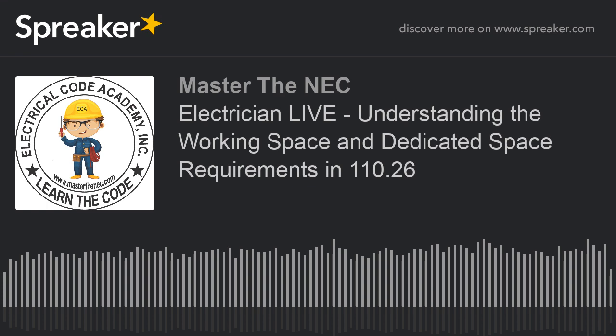So now we're going to read what it says here, and then we'll dig into the pieces of this. So it says working space. This is A. It says working space for equipment operating at 1,000 volts nominal or less to ground and likely to require examination, adjustment, servicing, or maintenance while energized. Okay, that's a key thing here. While energized, shall comply with the dimensions of 110.26(A)(1), (A)(2), (A)(3), and (A)(4). Obviously, we're going to discuss all of these. Or as required or permitted elsewhere in this code.